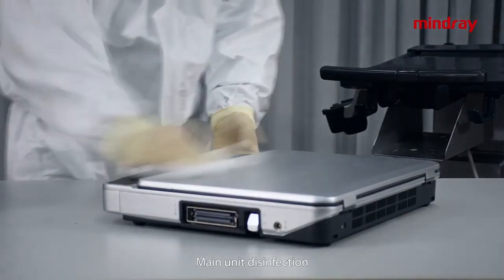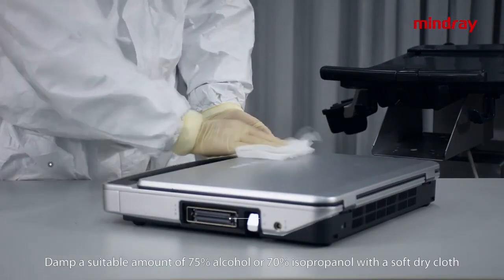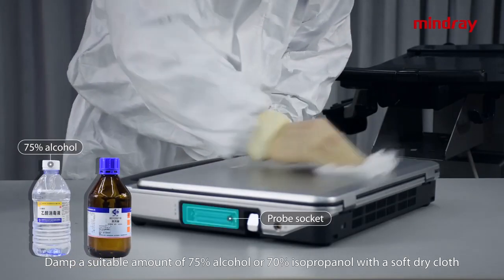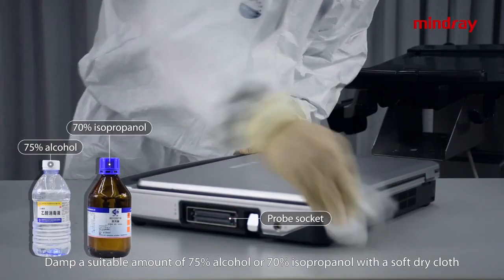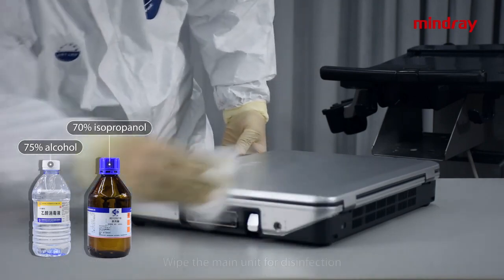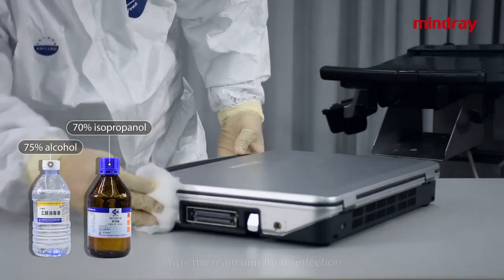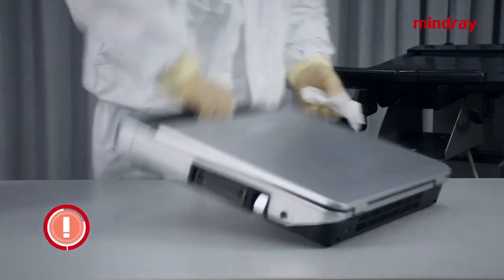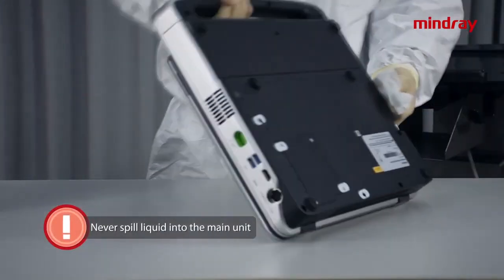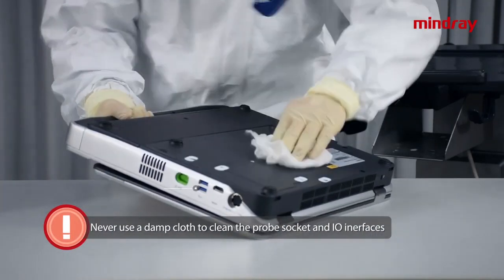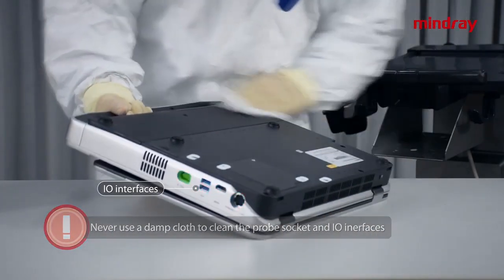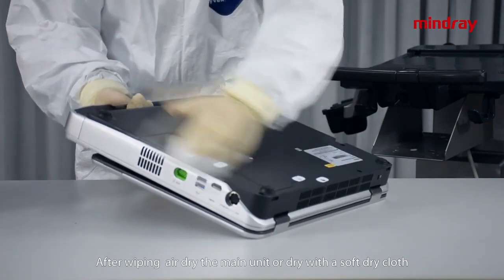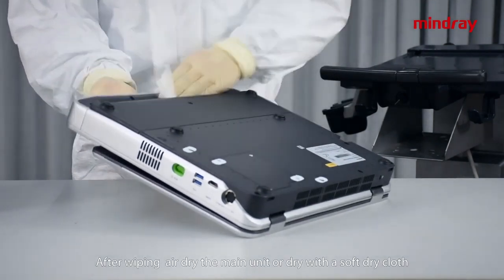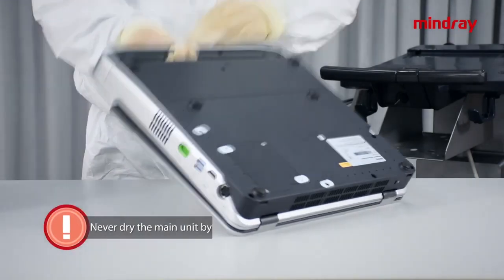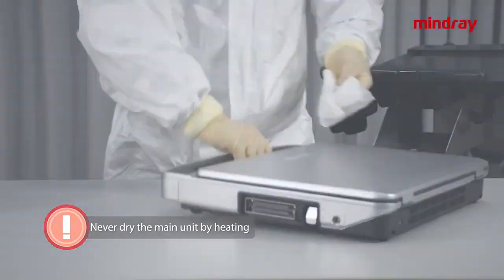Main unit disinfection. Dampen a suitable amount of 75% alcohol or 70% isopropanol with a soft, dry cloth. Wipe the main unit for disinfection. Caution: never spill liquid into the main unit. During disinfection, never use wet wipes to wipe the probe socket and I/O interfaces. After wiping, air dry the main unit or dry with a soft dry cloth. Never dry the main unit by heating.